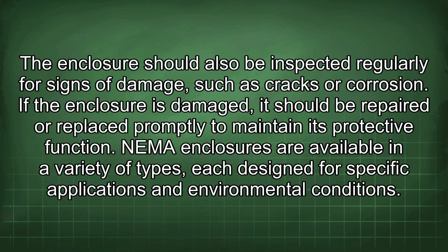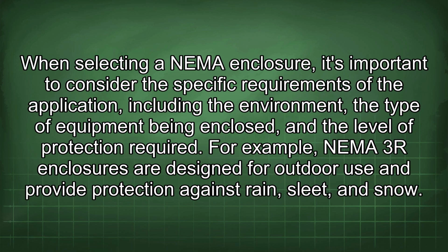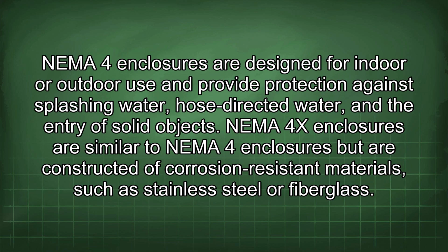NEMA enclosures are available in a variety of types, each designed for specific applications and environmental conditions. When selecting a NEMA enclosure, it's important to consider the specific requirements of the application, including the environment, the type of equipment being enclosed, and the level of protection required. For example, NEMA 3R enclosures are designed for outdoor use and provide protection against rain, sleet, and snow. NEMA 4 enclosures are designed for indoor or outdoor use and provide protection against splashing water, hose-directed water, and the entry of solid objects.